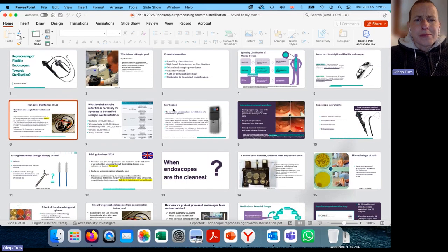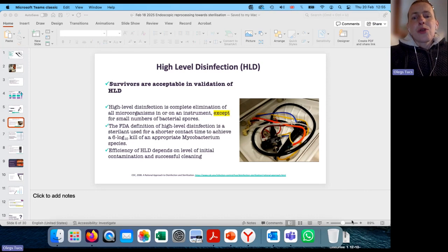Oh, let's jump here. High-level disinfection. So if you validate a high-level disinfection system, you need to prove as an engineer or as a manufacturer that the system actually kills microbes to an extent. Now, how much is that? That's a different question. Because if you go by the definition that high-level disinfection is complete elimination of all microorganisms in or on an instrument except for a small number of bacterial spores, I genuinely have a problem with this word, small, because this is not something you can validate. You cannot validate a small number, and a small number for you may be 10, a small number for me may be 1 or 100, who knows?